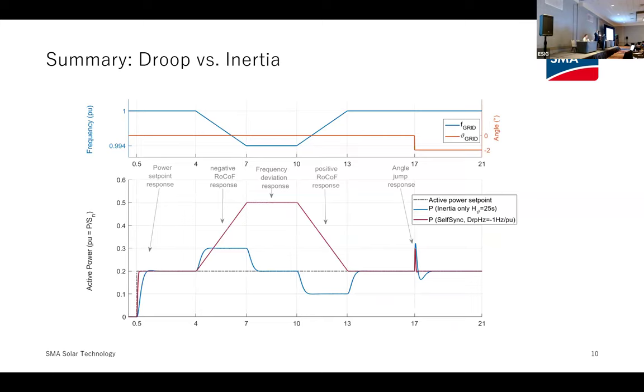I want to show you the difference between an inertial response and a droop response. The red line on the bottom graph is what the inverter is doing in droop mode, and the blue line is an inertial response. In droop, you are proportional to the change in frequency, whereas in inertial control mode, we're acting in proportion to the rate of change of frequency — the derivative. They're quite different and have different benefits to the grid in terms of bringing stability to the network.